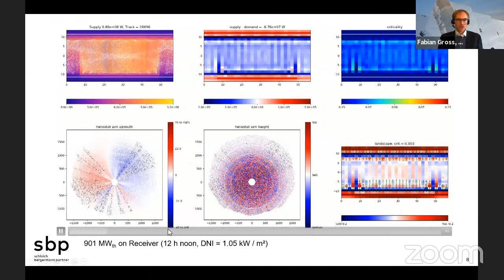What you notice is how a lot of white points move to the center. These are the outer heliostats with relatively big images that aim for the center of the receiver to have a high intercept. The close heliostats near the tower do most of the vertical aiming, providing enough power towards the higher and lower edges of the receiver circumference.